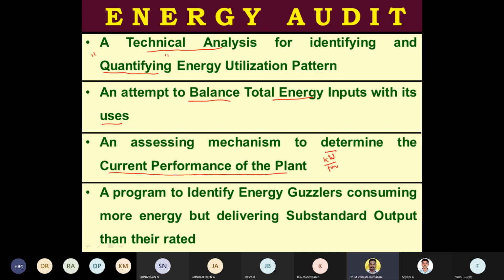What is the power consumption that the system has taken for every tonnage of refrigeration, kW per TR. Once you are able to establish this for your house, you can check whether it is on par with the latest ones. If there are problems in the condenser coil, evaporator coil, or filter, we'll be losing a higher amount of energy, and the COP or efficiency of the air conditioning plant would be lower. So this kW per TR will become higher. Energy audit is an assessing mechanism through which we'll be able to ascertain how we perform.